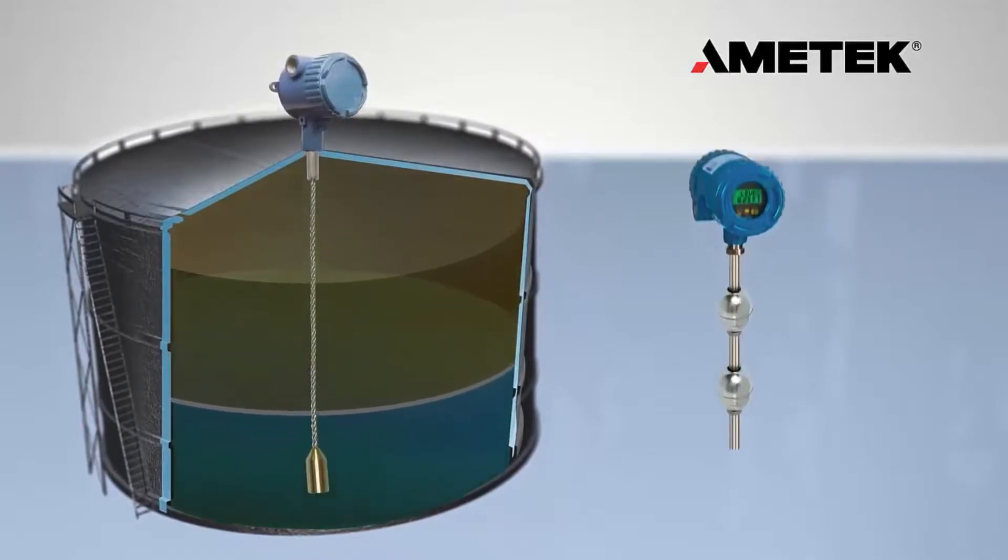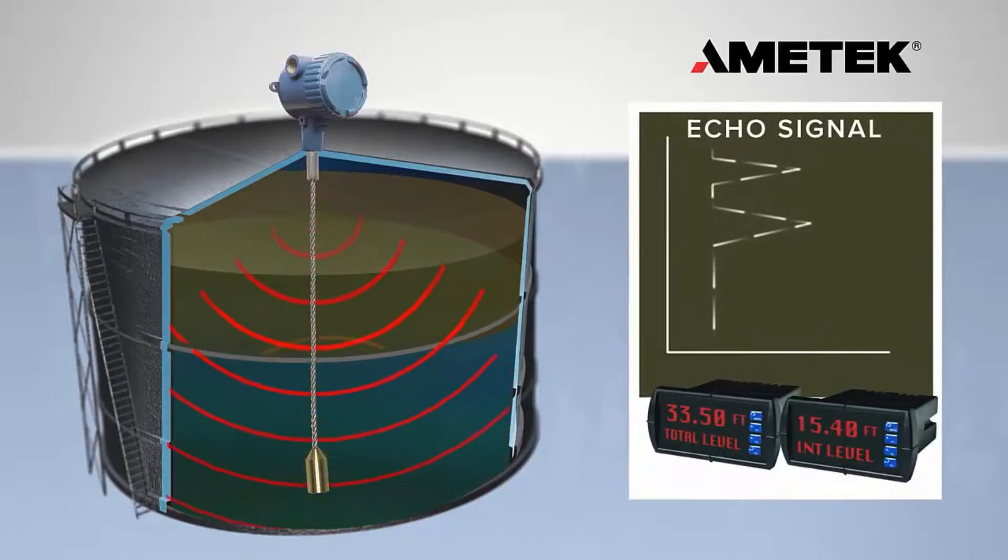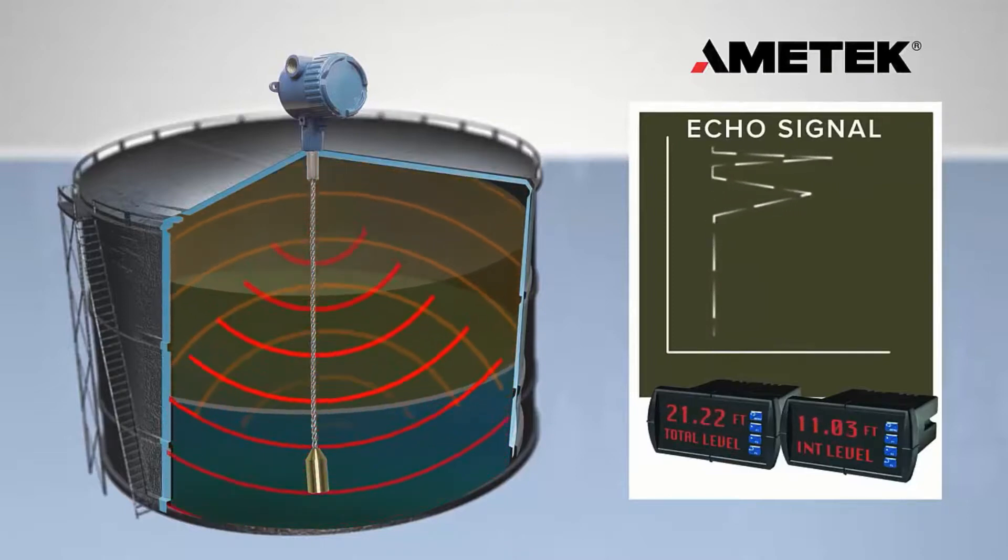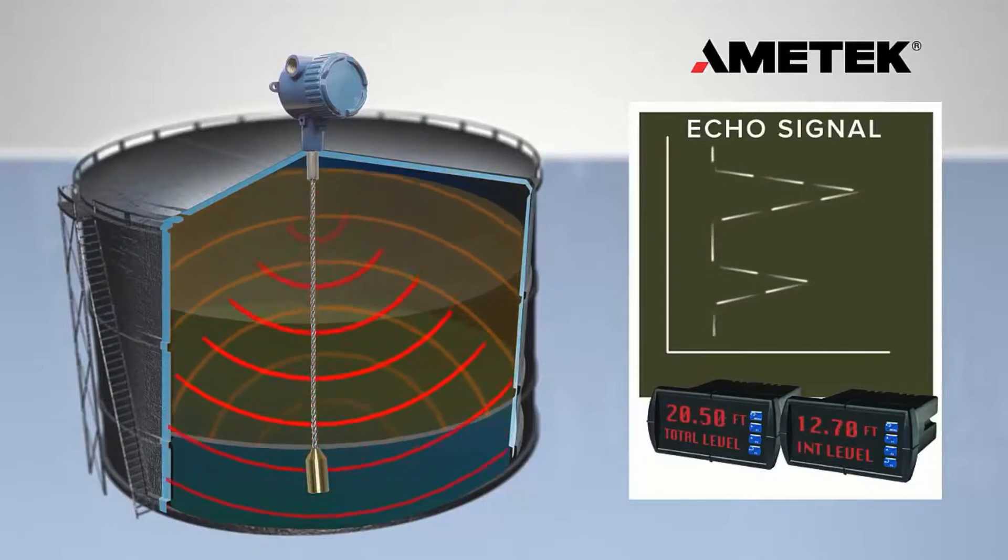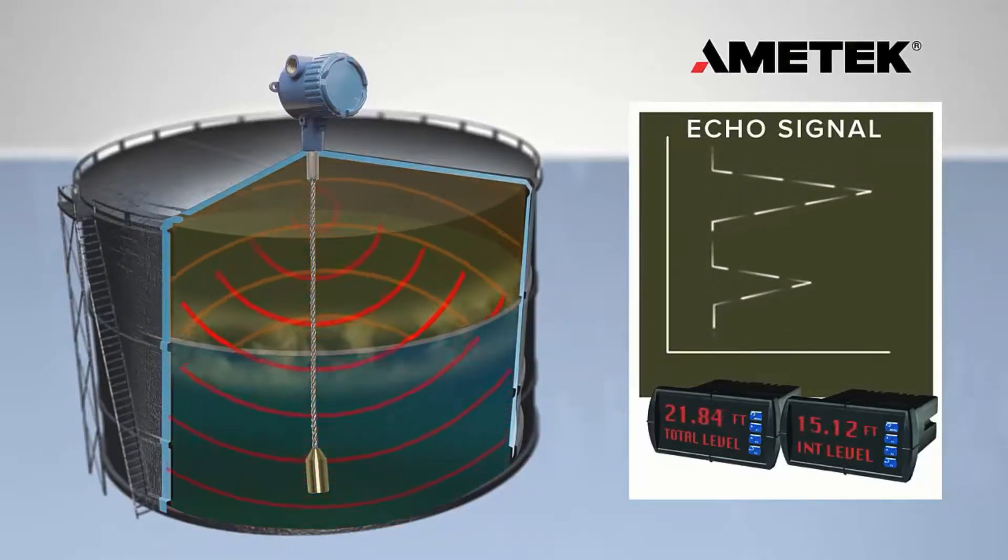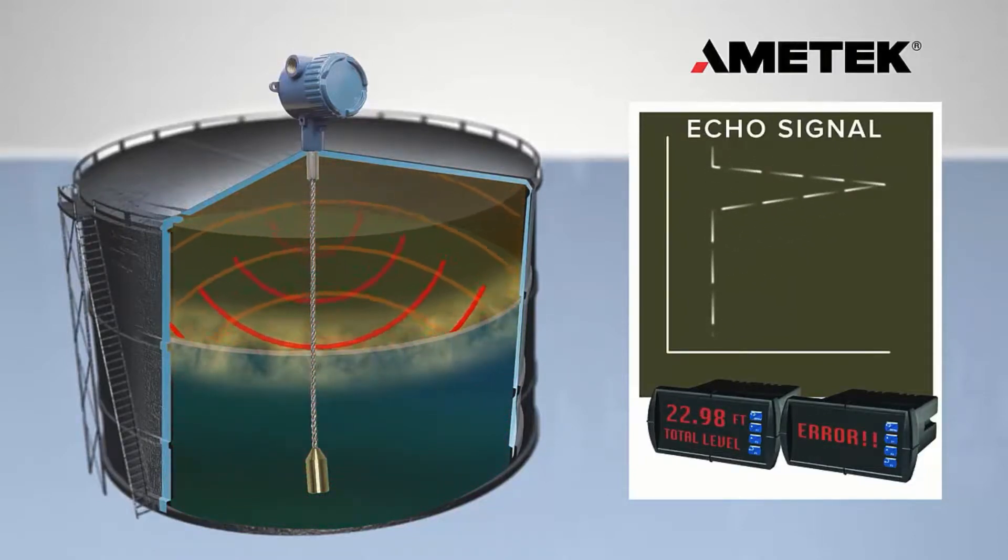Guided wave radar technology is based on microwave pulses that are transmitted down a probe and are partly reflected by the product surface as well as the interface level surface. In applications where both liquids have stabilized, guided wave radar technology can accurately determine both the product and interface level. If an emulsion layer forms between the two liquids, this can significantly diminish the measured value or even cause the complete loss of the signal.